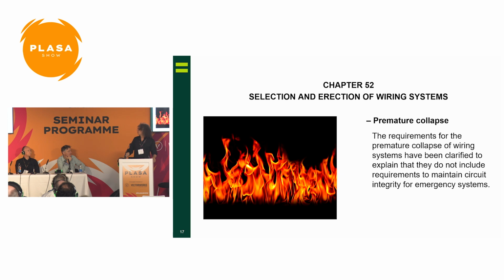in the cables. So what came in here was to avoid premature collapse in areas like that, where cables are routed across doorways, for example, that need to be held up by metallic ties or some form of strong mechanical construction that would stop premature collapse. So that's something to consider where cables are being run in and out of buildings and across door openings and stairwells, that kind of thing. So that's something that's gone in there.